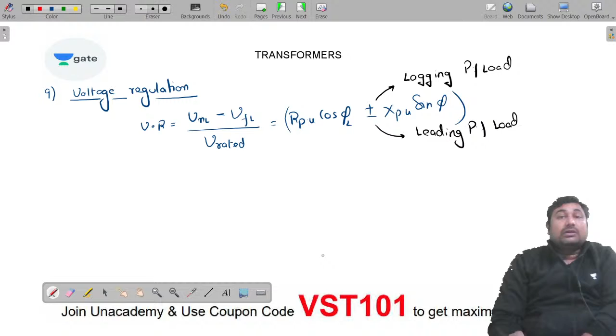Can we write V no load minus V operating? In case the transformer is a distribution transformer, it is not going to operate at full load. Under that condition, we represent no load minus V operating upon rated voltage as R per unit cos phi 2 plus minus X per unit sine phi 2. But I am not going to call this the voltage regulation. This expression can be useful to find the relation between the output voltage under different loading conditions, but we don't call this the voltage regulation.